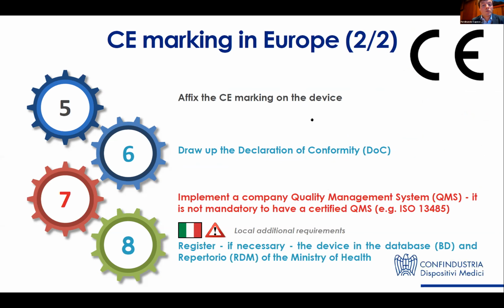The manufacturer will have to draw up the declaration of conformity, a declaration with which the manufacturer declares that he complies with the relevant directives and the technical standards, and puts the device on the market under his own responsibility. Then as an organization, you will have to implement a quality management system according to ISO 13485.